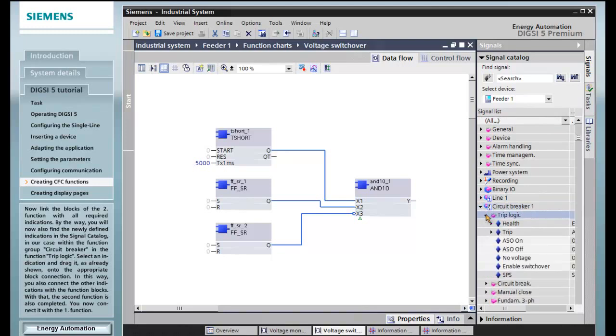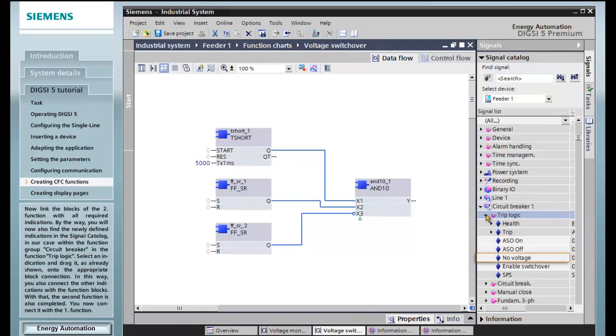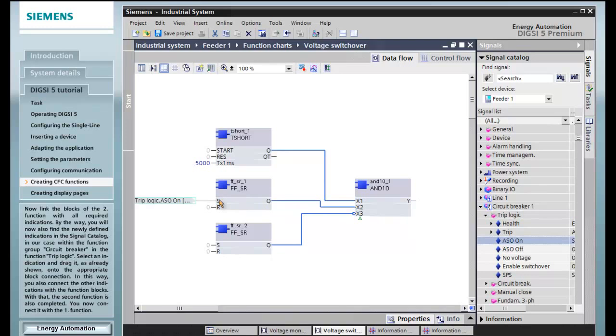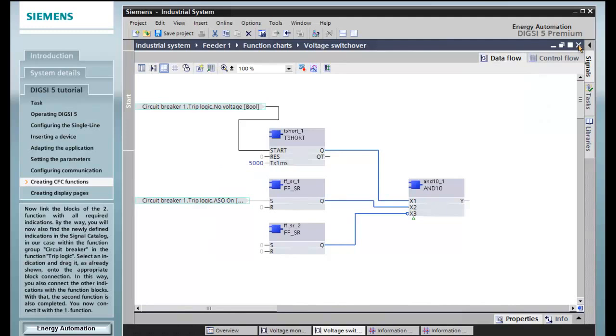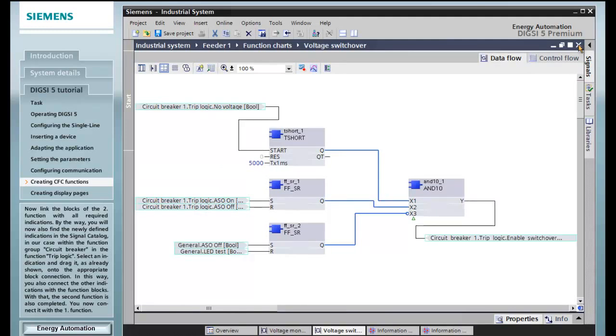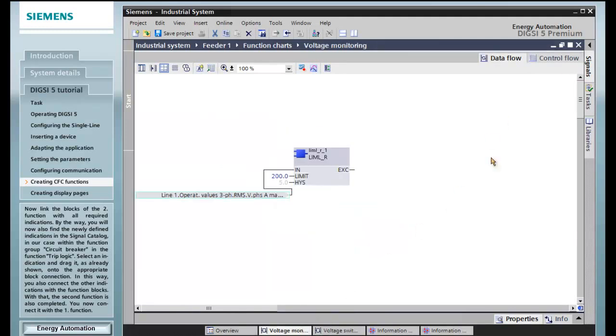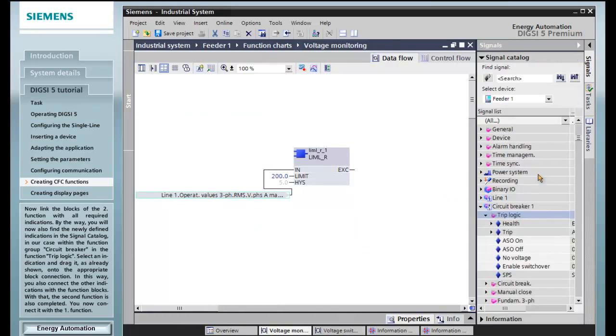Now link the blocks of the second function with all required indications. By the way, you will also now find the newly defined indications in the signal catalog, in our case within the function group circuit breaker in the function trip logic. Select an indication and drag it, as already shown, onto the appropriate block connection. In this way, you also connect the other indications with the function blocks. With that, the second function is also completed. You now connect it with the first function.